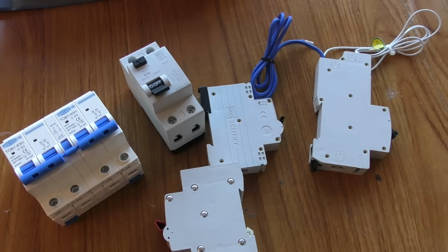I think at very worst it would be a C3, which is the code for improvement recommended, unless what you put in there was something actively hazardous. As long as it's electrically sound, and the thing itself has the appropriate approvals and meets the standards, I think it's quite hard to argue that it's really an issue putting a different manufacturer's changeover switch into an existing consumer unit. If the manufacturers produced this kit, I'd be more than happy to fit it, but in my case it wasn't possible.